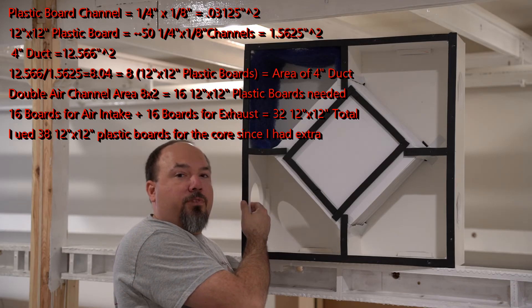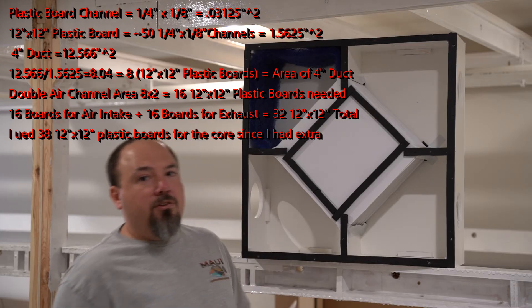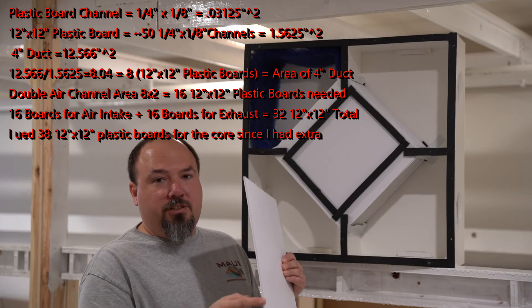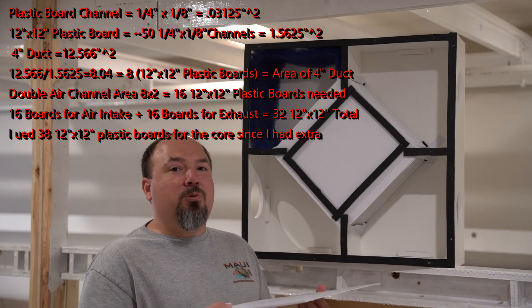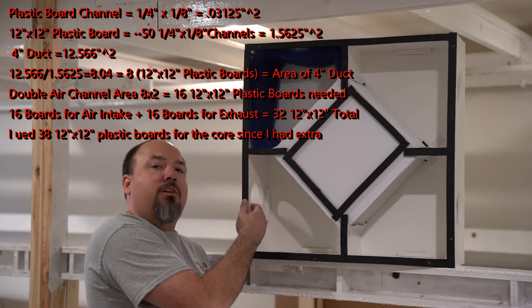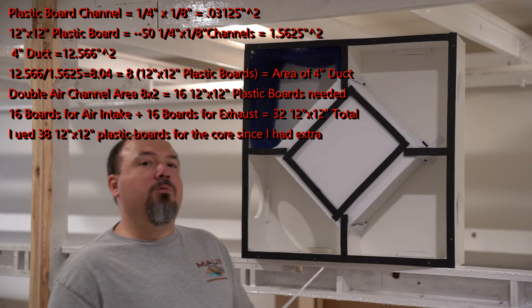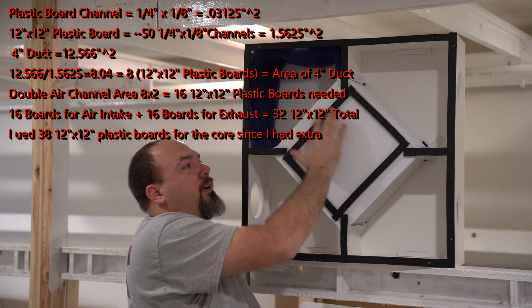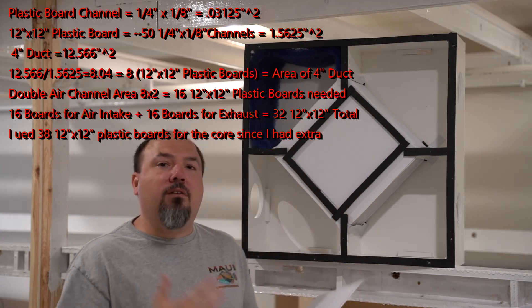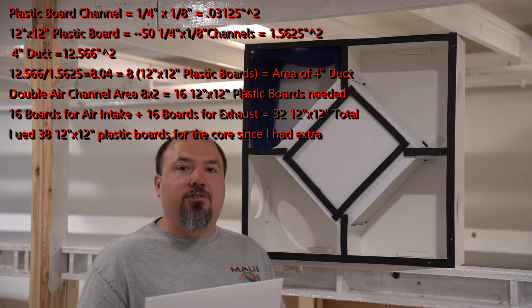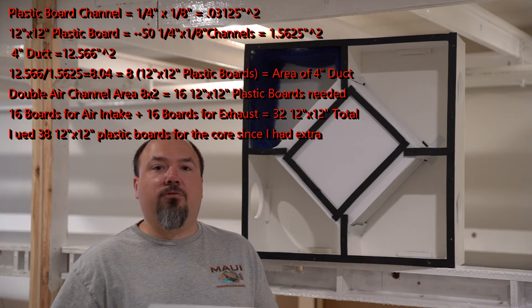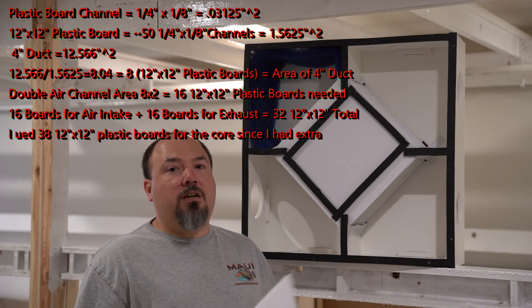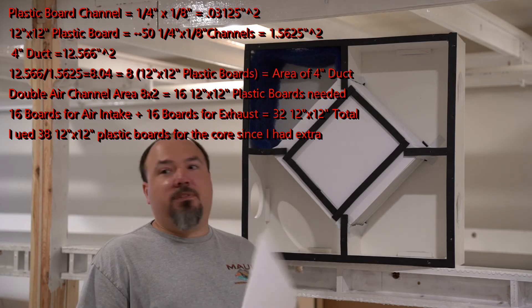So it's really important to know the area inside of one of these sheets because what you need to do is also figure out the area of a 4-inch diameter hole for the duct. So once you figure that out in square inches, you can calculate the square inches for each one of these sheets. And what I did was I doubled the number of square inches over the square inches of the duct. What this will do is allow the air to come into the HRV. And when it enters the core, it can slow down a little bit because it has such a wide passage to go through before being re-accelerated out when it goes into a smaller duct.